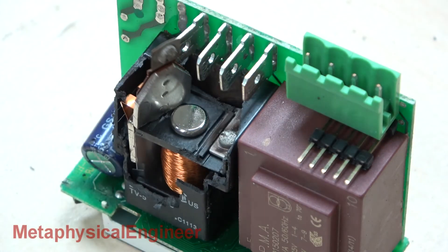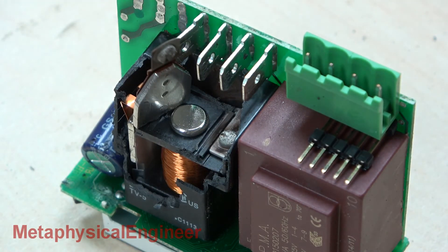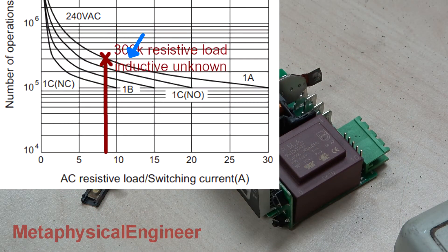Taking into account the derating and how it was not tested for motor load conditions, even though this is a 115 volt motor at only single digit amps, it's no wonder the relay has failed.